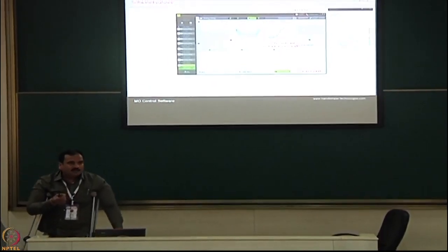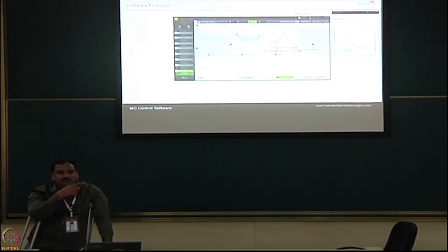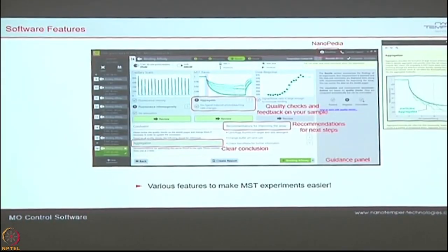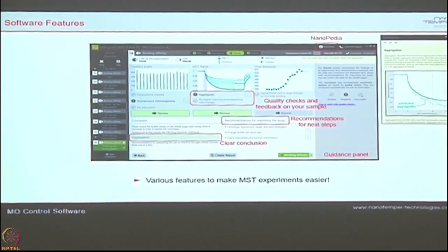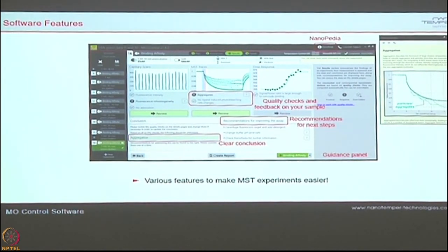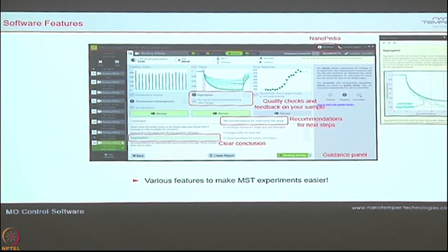If your samples are making aggregates at a particular concentration when interacting with the ligand, the sample will be non-homogeneous. The thermophoresis behavior will be very random — the curve looks very wavy. Qualitatively we can always judge the aggregation of your sample. The biggest advantage here is you are using different independent capillaries for every dilution — if one capillary has an aggregate, you can discard it and know at what concentration your protein is actually aggregating.